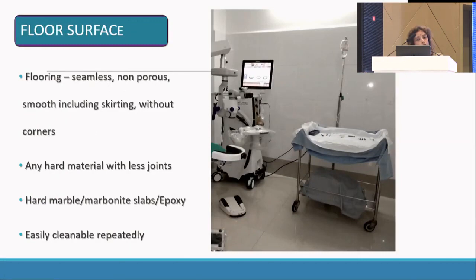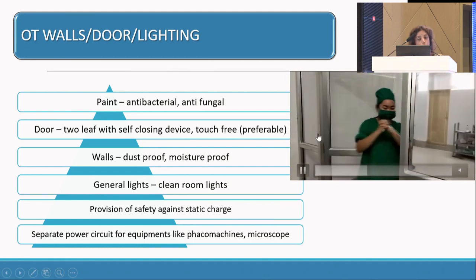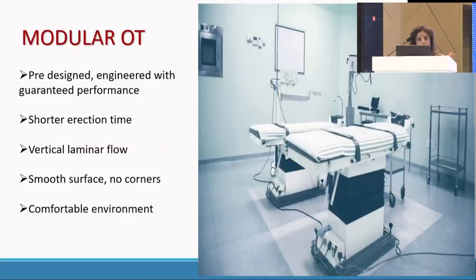Floor surfaces of the OT should preferably be tiles so that they are non-porous, seamless, and easily cleaned day after day. OT walls should be dust-proof and moisture-proof, with good lighting. Doors should be self-closing with a door closer so that your OT nurses don't have to keep them open. Since we are dealing with costly machines like phaco and vitrectomy, there should preferably be a separate power circuit with a UPS backup. A modular OT for those who can afford it is great — it has guaranteed performance, shorter erection time, and vertical laminar flow.